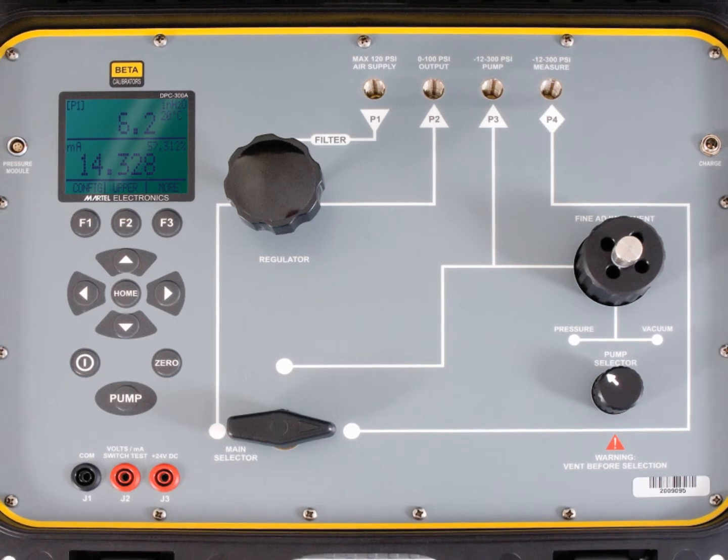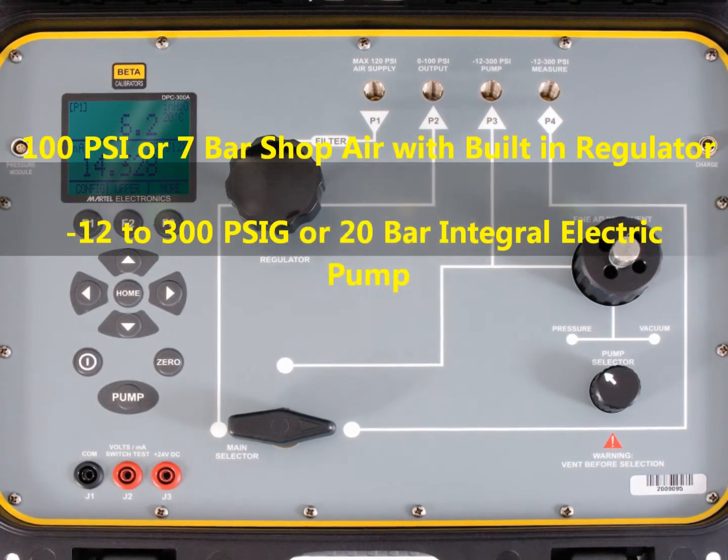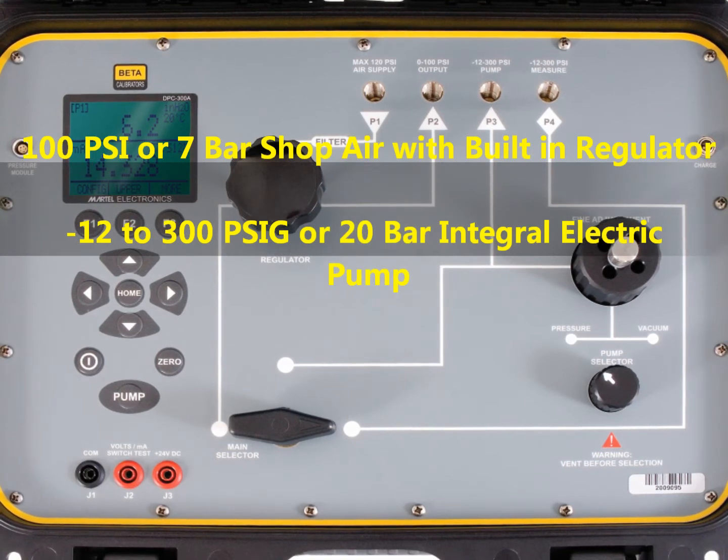By dual system, we mean the calibrator can be used with shop air up to 100 psi or the internal pump which handles up to 300 psi.